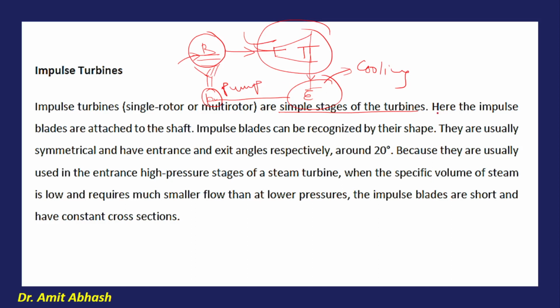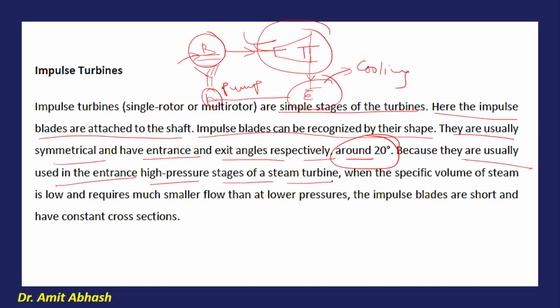Now the second point: the impulse blades are attached to the shaft. Impulse blades can be recognized by their shape—they are usually symmetrical and have entrance and exit angles respectively around 20 degrees. I already discussed these things inside the classroom. So the symmetrical shape of the impulse turbine means the blades have a symmetrical shape with entrance and exit angle the same, around 20 degrees, because they are usually used in the entrance high pressure stages of the steam turbine when the specific volume of steam is low and requires much smaller flow than at lower pressure. The impulse blades are short and have constant cross-sectional area. How it looks, we will see.